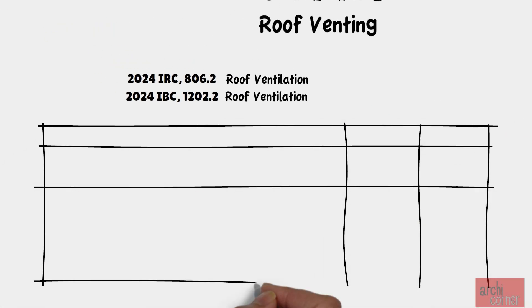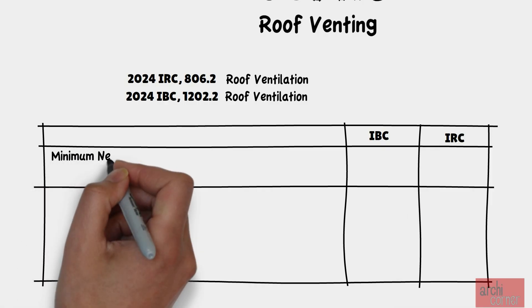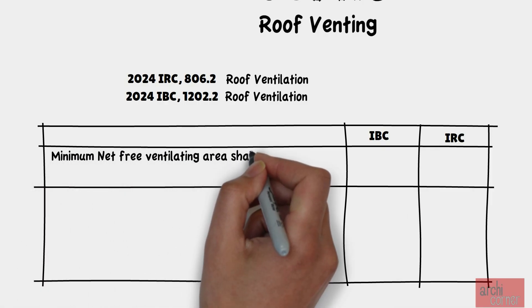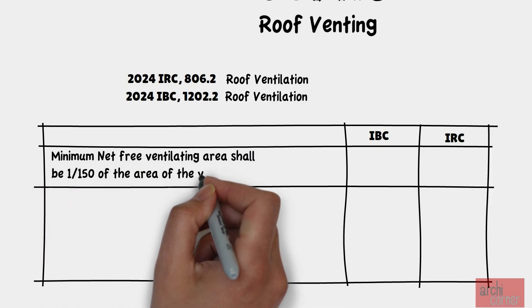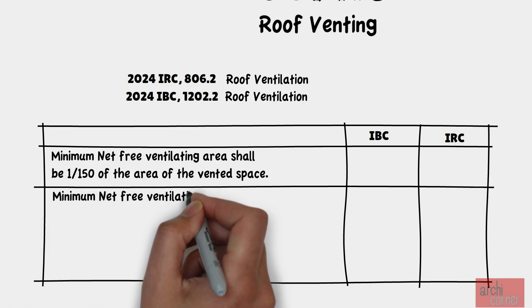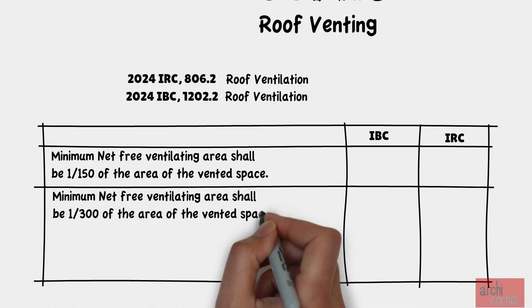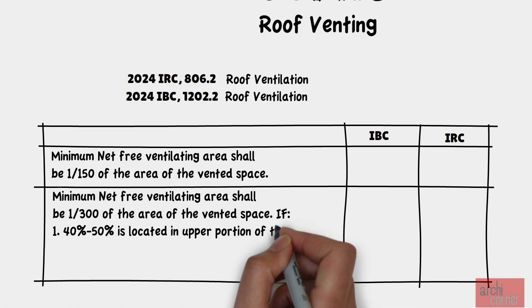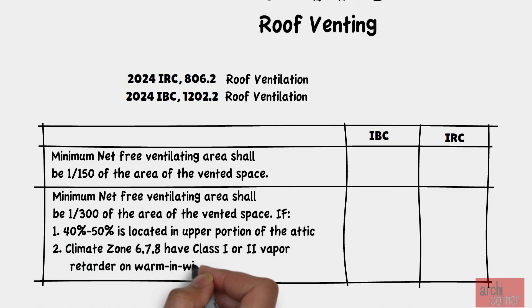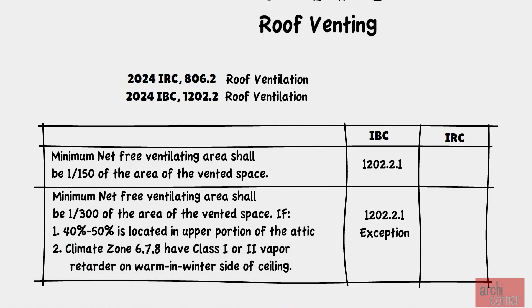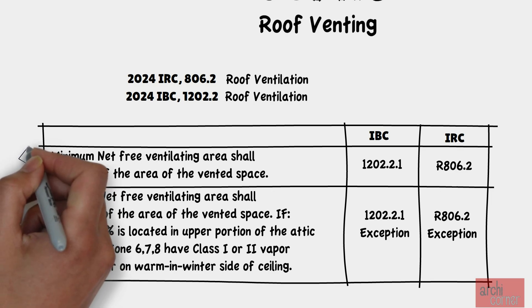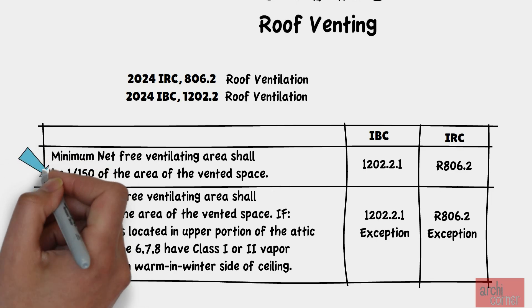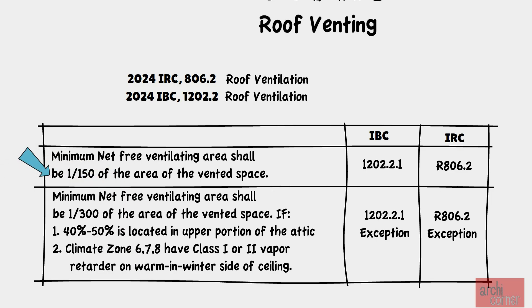As I was saying, there are basically two options. The first option is having most, if not all, of your venting on the lower portion of the roof. The second option is to only have between 40 to 50% of the venting on the upper portion. In the first option, the minimum net free venting area shall be 1/150th of the area of the vented space. Depending on whether you are referencing the IBC or IRC, here are the code sections.